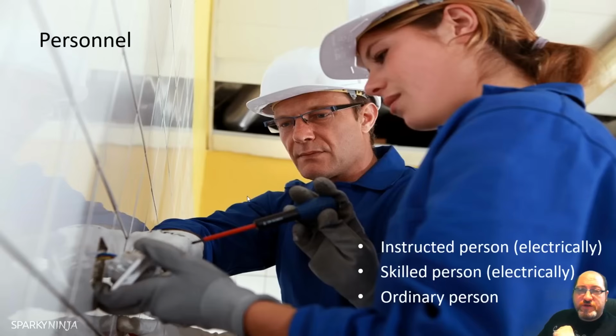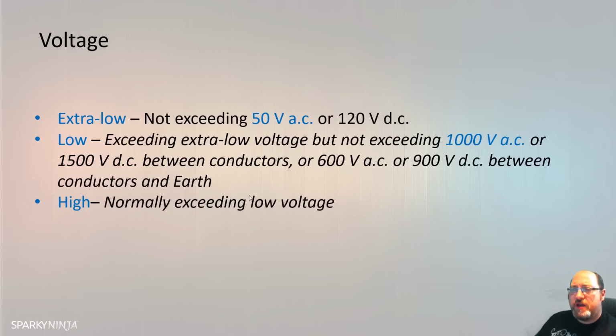There's also definitions on voltage. Now, I mentioned earlier, in the introduction video or part 1 video, I can't remember, where low voltage goes up to 1000 volts AC and 1500 volts DC. That was between live conductors. It's 600 volts or 900 volts between a live conductor and earth. When we go over that, we're then in what's known as high voltage from BS7671. Now, people in high voltage may say, oh, you've got medium volts and high volts, but from the BS7671 perspective, we are low or high.